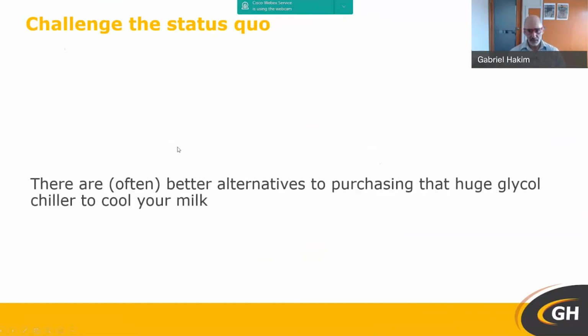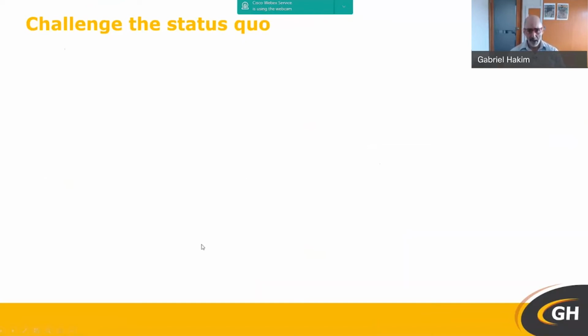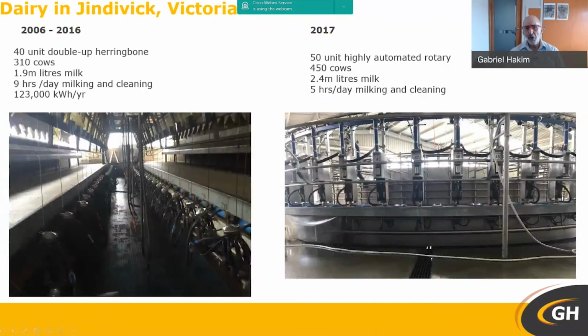Don't opt for a huge glycol chiller. I've seen chillers now around 120 kilowatts because people say that's the only way to cool milk. Well, it's not. With this dairy, we opted for a 12 kilowatt chiller. Everyone said we couldn't cool the milk unless we had an 85 kilowatt chiller, but we've done the same job using probably 20% of the energy that would have been used with that chiller.